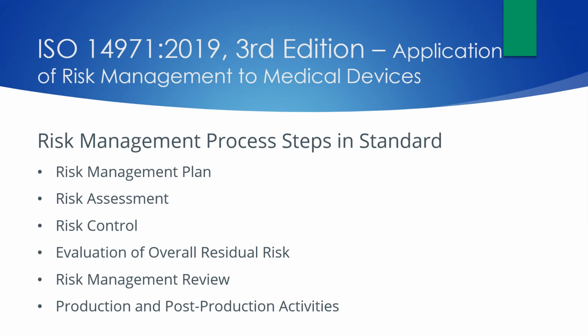Risk assessment includes risk analysis and risk evaluation. Risk analysis includes the documentation of a medical device's intended use. Risk evaluation includes assessment of risk using criteria for acceptability. Risk control is the reduction of risk to an acceptable level. Examples of this include designing the device to be inherently safe, ensuring that hazardous situations can't occur, or implementing protective measures. The evaluation of overall residual risk includes analyzing the contributions of all individual risks to ensure several small risks do not create an unexpected larger risk. The risk management review is the review of the risk management plan to ensure it was properly executed and documented and that the residual risk is acceptable.